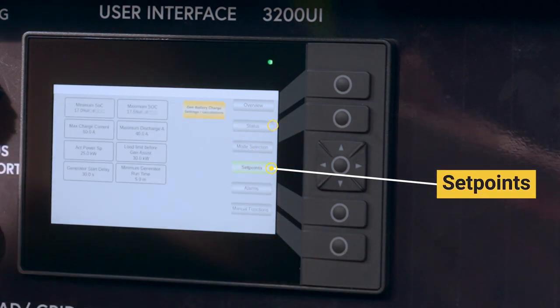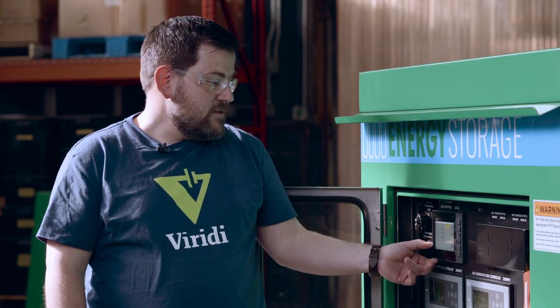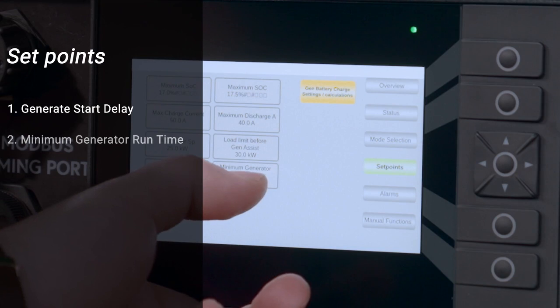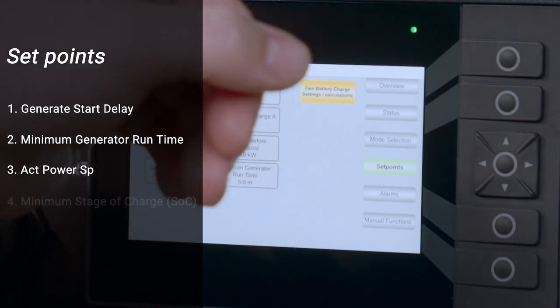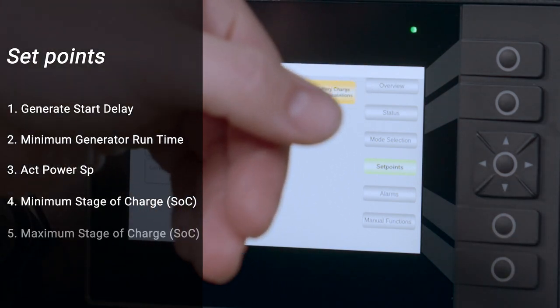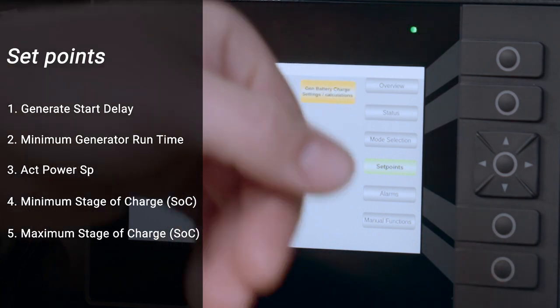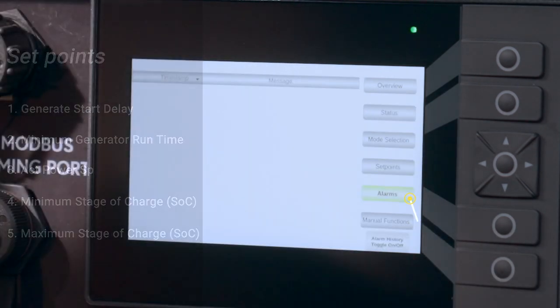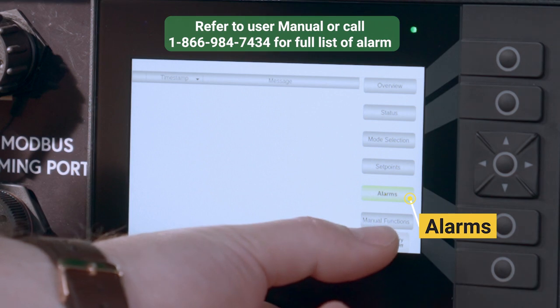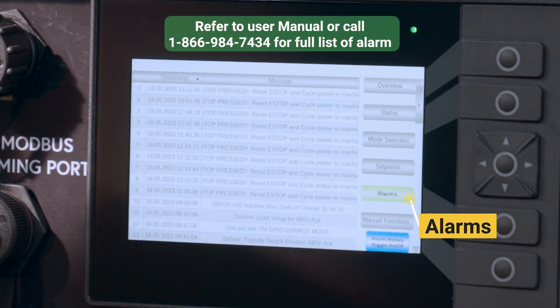Set points is where you'll make some adjustments based on what you are doing in different modes. You have your generator start delay, your generator minimum runtime, your active power set point, and your minimum and maximum state of charge used in your generator hybrid mode. Alarms will show what the active alarm is, and you can also go into the history and see the history of what has occurred on the machine.